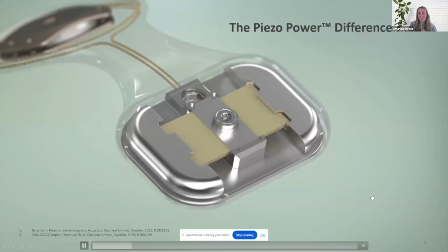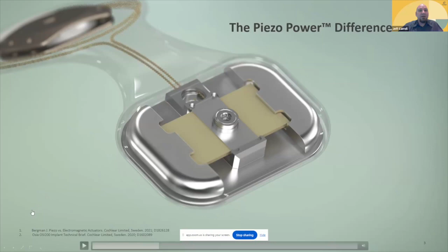Well, and especially when it comes to MRI, don't move ahead yet, Amanda. We focus a lot on the magnet end for MRI compatibility. And as we talked about in this talk, the OSI 200 was compatible with a head wrap for MRI at 1.5 Tesla. But what doesn't get shared a lot or enough, in my opinion, is that without a magnet, if you were to take the magnet out of an OSI 200 or OSI 300, the Osia body, the part that we're looking at right now, has always been MRI compatible all the way back to the first generation, because there's no magnetic components. None of these pieces of metal that you're seeing are magnetic or ferrous metal. It's titanium and tungsten. So this has always been MRI compatible, which means you put that into an MRI, it's going to function the same coming out of the MRI as it would have going in.